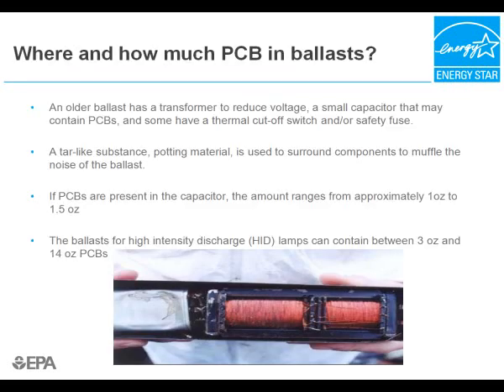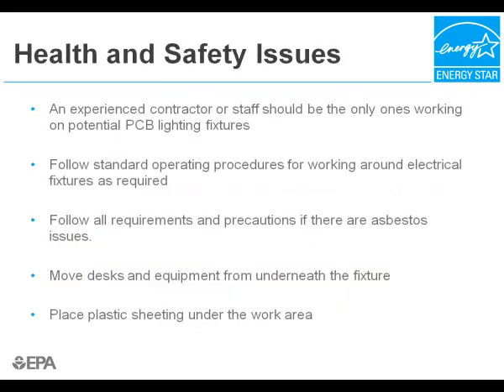PCBs are found in these old ballasts in the small capacitor, and the amount ranges from 1 ounce to 1.5 ounces. The tar-like substance of the potting material is used to surround the components to muffle the noise of the ballast. Thermal-protector switches were commonplace in the mid-1980s, but EPA found thermal switches in some ballasts manufactured in the early 70s. These ballasts appear to leak less since they do not get as hot, but unfortunately, if they are leaking and get hot, they shut down, cool down, reset, and continue to work and continue leaking. How do we safely handle the removal of these lamps or ballasts?